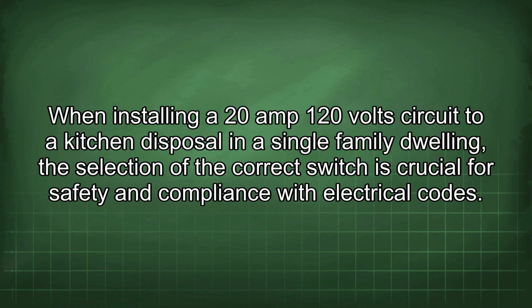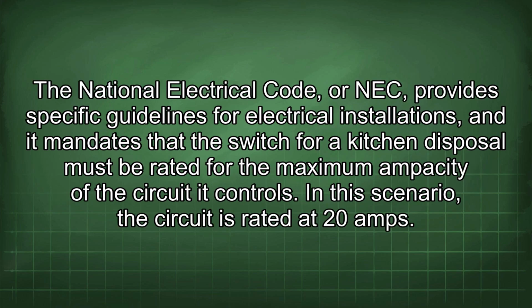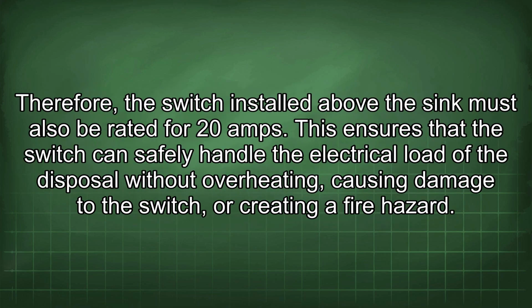When installing a 20 amp 120 volt circuit to a kitchen disposal in a single family dwelling, the selection of the correct switch is crucial for safety and compliance with electrical codes. The National Electrical Code, or NEC, provides specific guidelines for electrical installations, and it mandates that the switch for a kitchen disposal must be rated for the maximum ampacity of the circuit it controls. In this scenario, the circuit is rated at 20 amps. Therefore, the switch installed above the sink must also be rated for 20 amps.